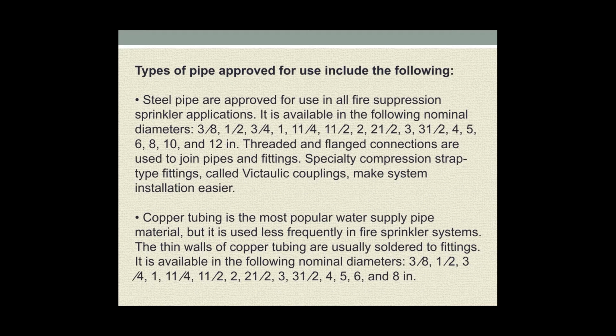Types of pipe approved for use include the following. Steel pipe is approved for use in all fire suppression. Sprinkler application is available in the following nominal diameters: 3/8, 1/2, 3/4, 1, 1 1/4, 1 1/2, 2, 2 1/2, 3, 3 1/2, 4, 5, 6, 8, 10, and 12 inches. Threaded and flanged connections are used to join pipes and fittings, Specialty compression strap-type fittings called Victaulic couplings, which make system installation easier.